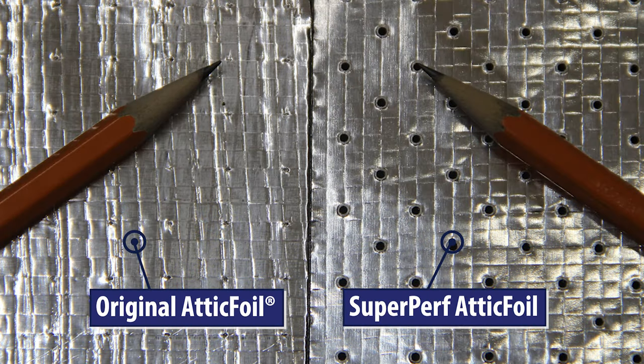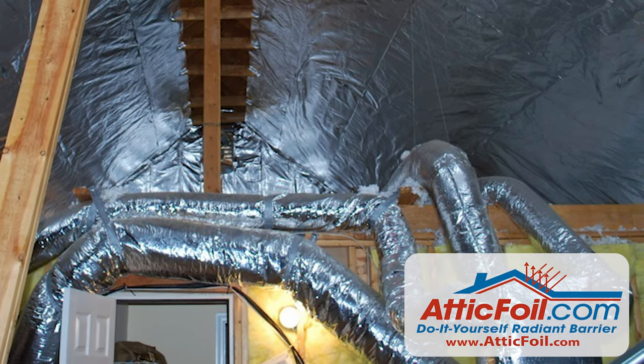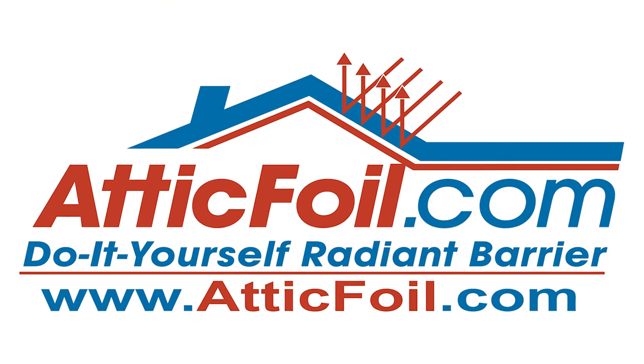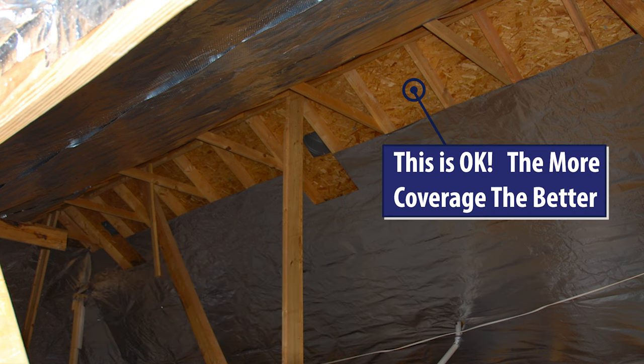Now, if you have ductwork in the attic, stapling it up is usually a better method because it puts the ductwork in a less hostile environment. If you staple it up, don't overthink it. It doesn't matter if you start at the top or at the bottom, if it's crooked or wrinkled or ugly, or even if you don't get the whole attic. Attic foil has a cumulative effect.